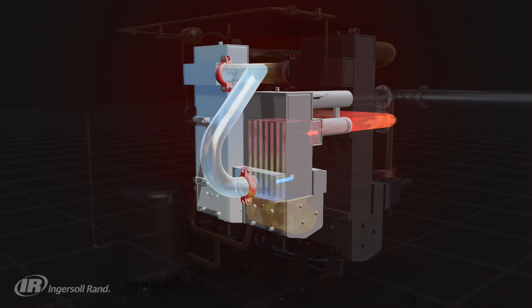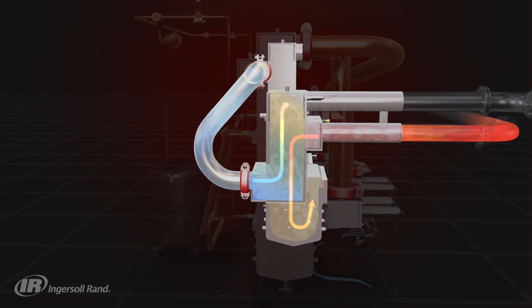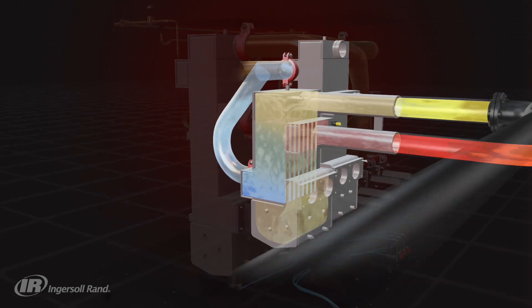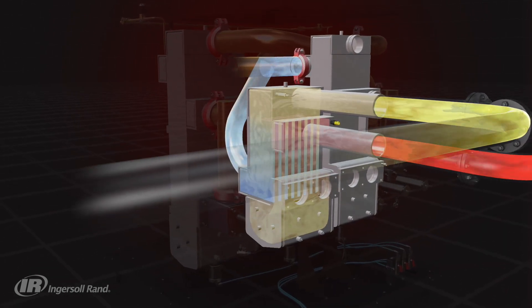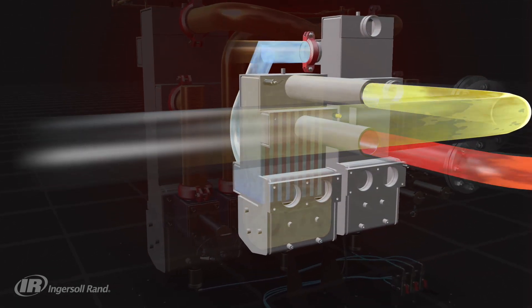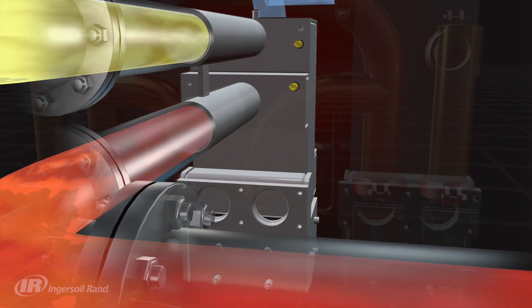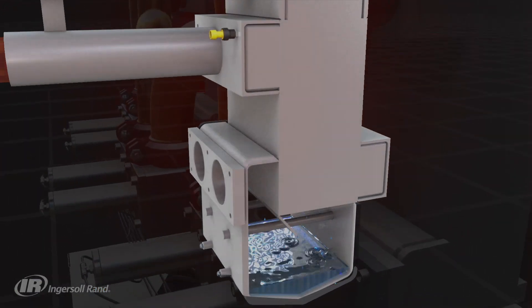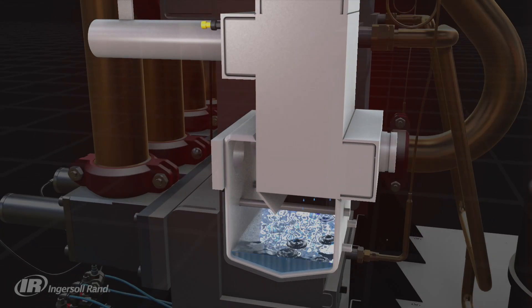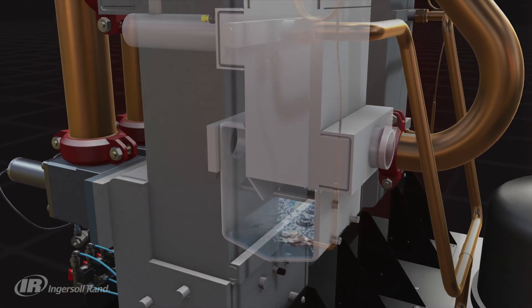This ensures the air exiting the dryer at a pressure dew point of minus 20 degrees Celsius is at an acceptable temperature. It also has the effect of partly cooling the incoming air, allowing for the efficient release of around 85% of its moisture content, which drops to a reservoir and is drained from the dryer.